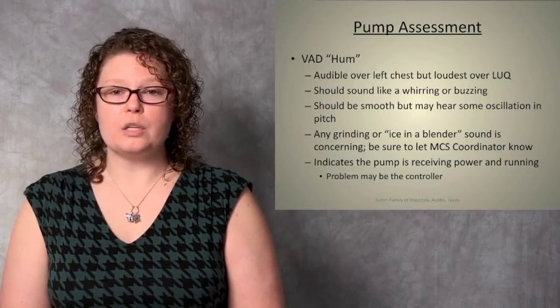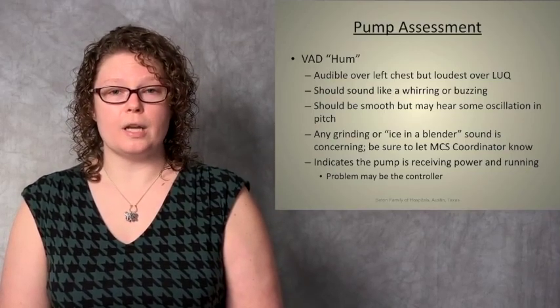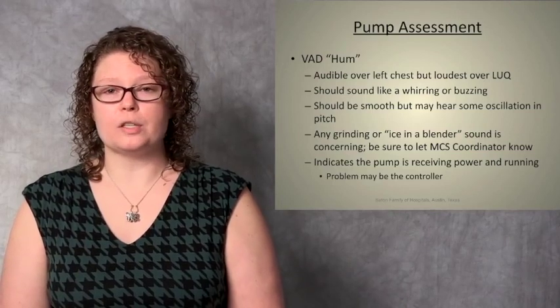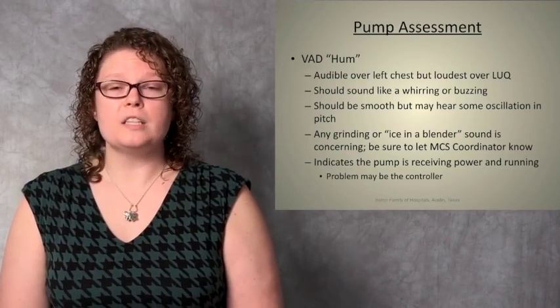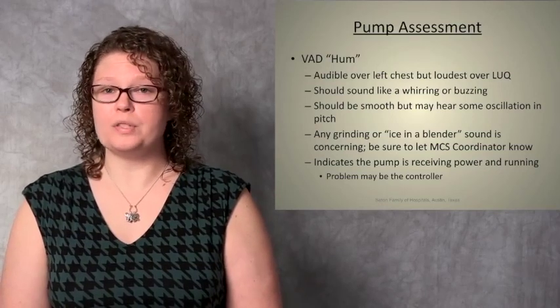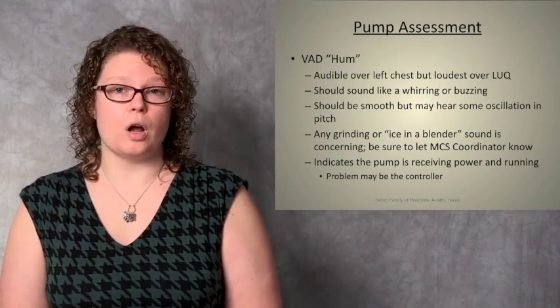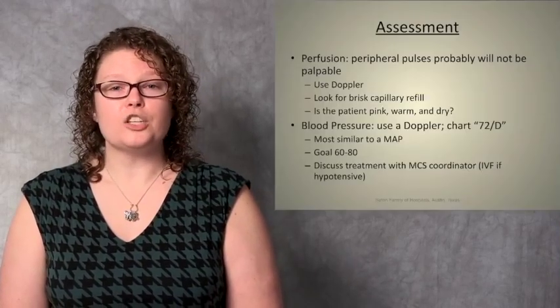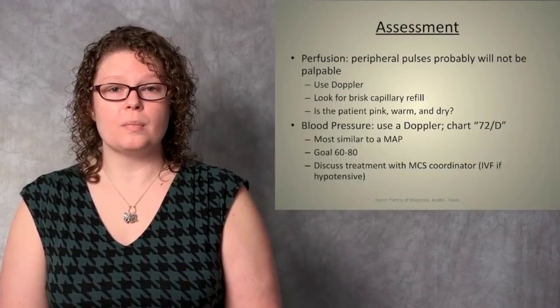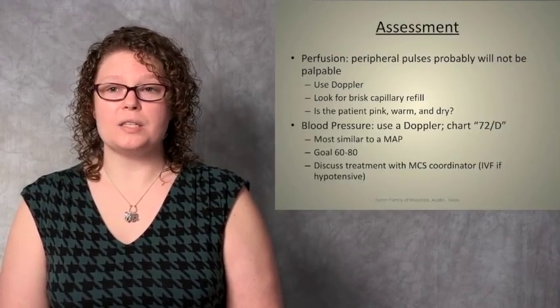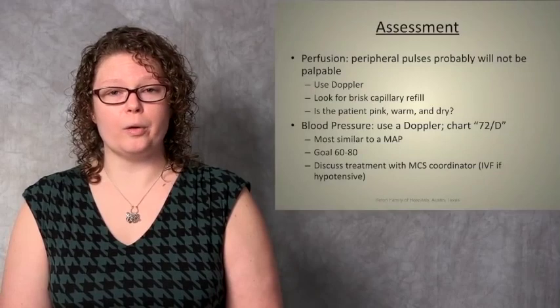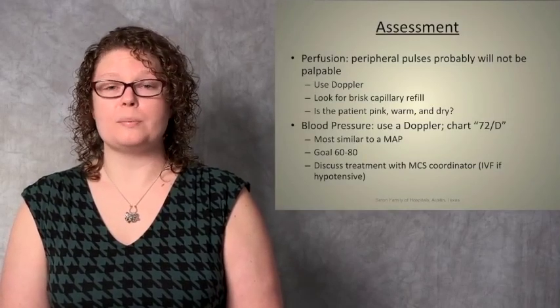It has a mechanical sound to it, but it should have a smooth, constant pitch, and any grinding or ice in a blender sound is extremely concerning for clot. Listening for the hum is a way to verify whether or not the pump is working if there's a malfunction with the controller and you're not sure. When we assess these patients, there are a few key differences to be aware of. These patients probably will not have a palpable pulse. Using a Doppler is the best way to assess for circulation, whether it's a general assessment or during CPR and ACLS. Other signs of perfusion that you can look for in your patient include capillary refill and looking to see that your patient is pink, warm, and dry.